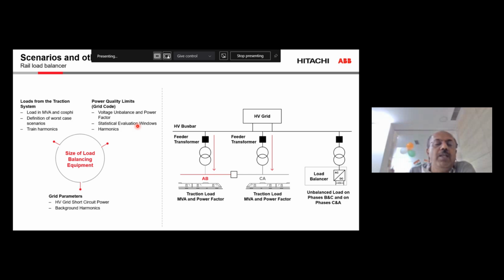For example, it is 10 minutes or 1 minute, what is that we need, and then what kind of harmonics levels we are expecting as a grid code requirement, and then grid parameters like what is the short circuit power and what all the background harmonics present in the network. So these are the influencing parameters which will decide what is the size of this load balancer.